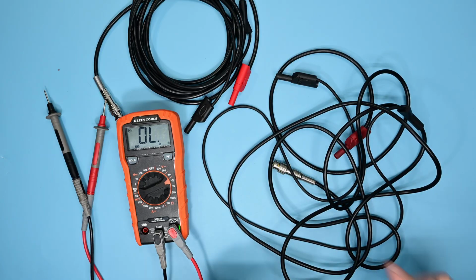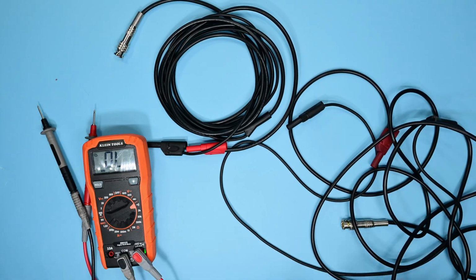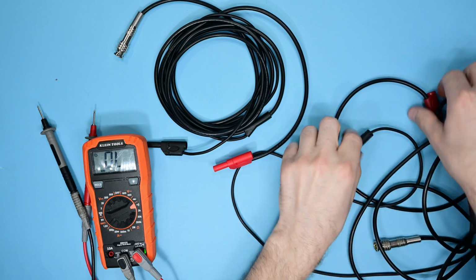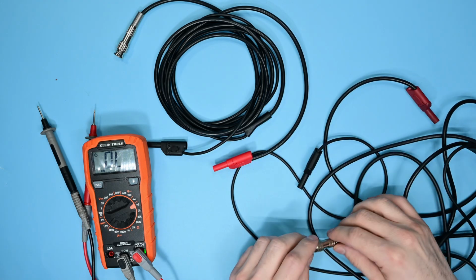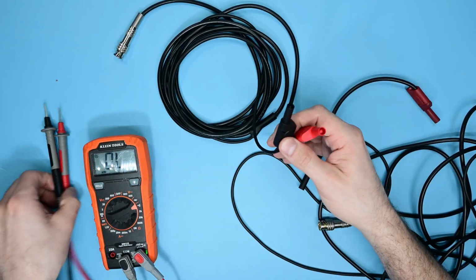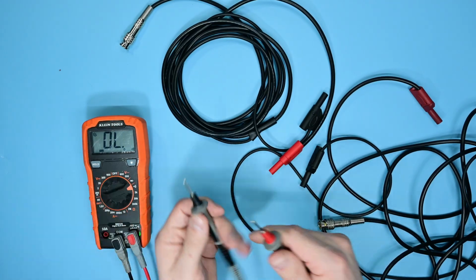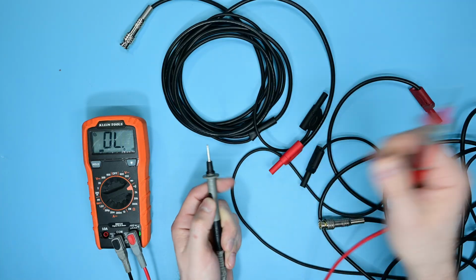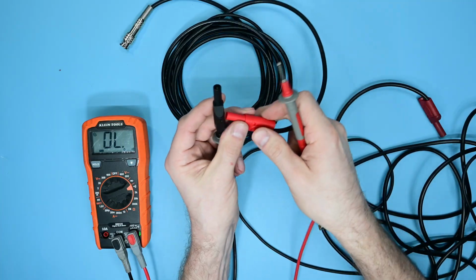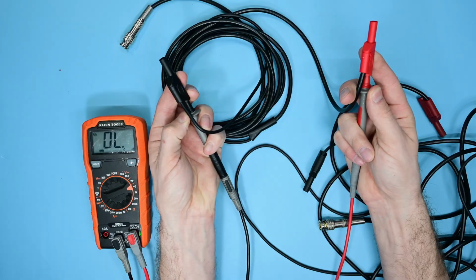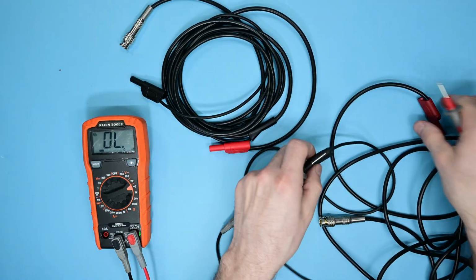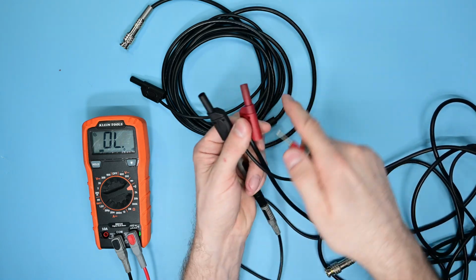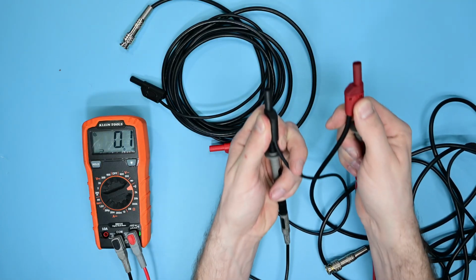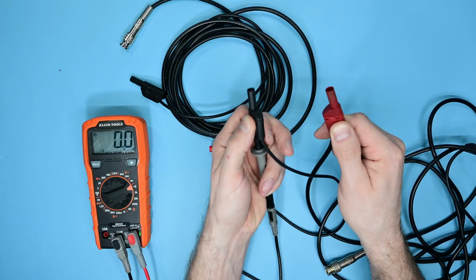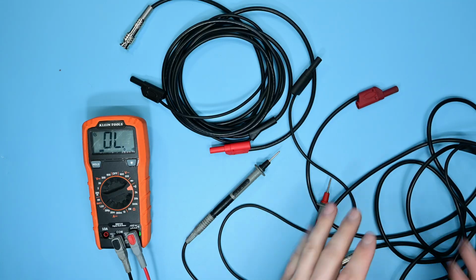One of the first things you need to do anytime you use any type of leads, or really any tool, is check its integrity. I have here a good set and a faulty set of these leads. These are supposed to have power and ground, and they should not connect anywhere in this wire, only to your scope. With a good set, I've set my multimeter to continuity to tell us if the wires are connected, which they shouldn't be. I'll probe my wires right there, not expecting anything, since there shouldn't be a connection. These tend to short out from time to time, and look at that, we have continuity. At best that gives us faulty readings, and at absolute worst it will short circuit our scope and wear out however much money that scope cost.